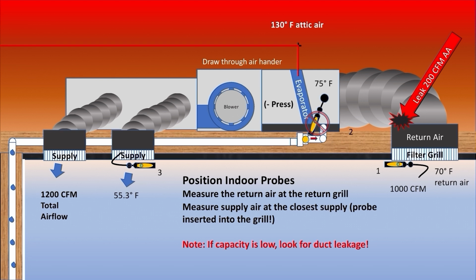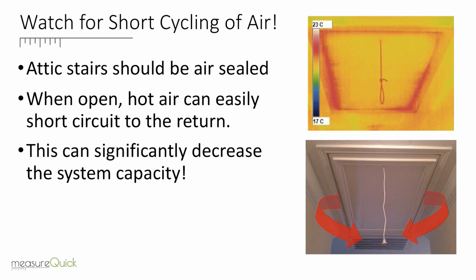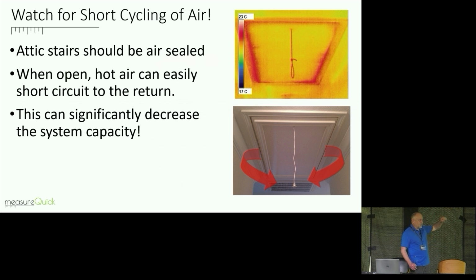Same thing here if we have an attic installation, right? We want to have the return air measured at the inlet to the filter grill, and then the really, really critical thing is to get that probe up inside the supply, okay? If your capacity is low, you're going to look for duct leakage. Short cycling of air. I've been bit by this more times than once, where I've gone up, pulled down the attic stairs, or not paying attention to the attic stairs. You put the probe at the ceiling.